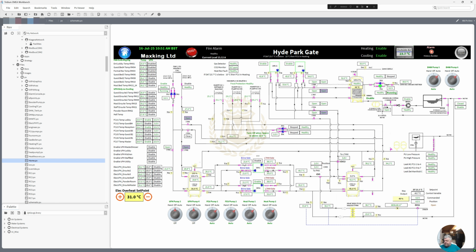So what we can only do with this hot water here that this is producing is we're running cold water supply through the one end of the plate heat exchanger, coming in at 23.5, but again that's a strap on, so I would say the cold water will be 16, 17, 18 degrees, and we're heating that cold water and putting it straight down to drain with the CV11, and that's the only way that we can actually get this heat pump to work without putting an outdoor unit, and we wasn't allowed to install outdoor units. So that's giving you a little bit of an example of the system and what we're trying to do with it.